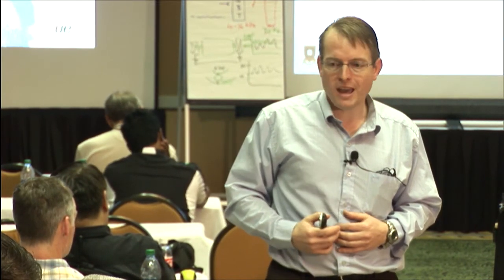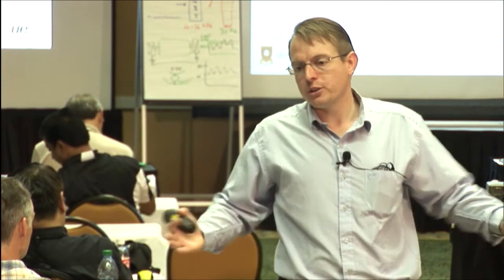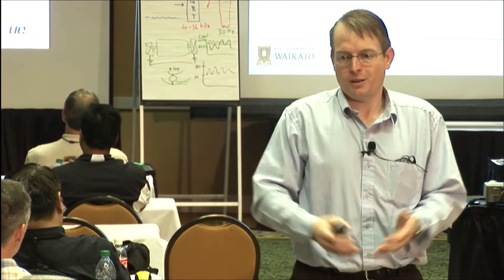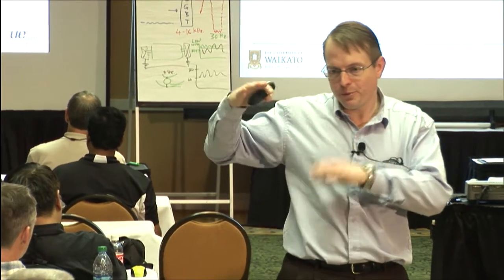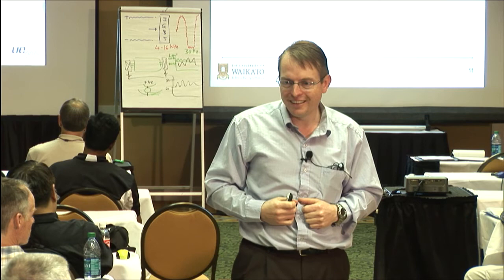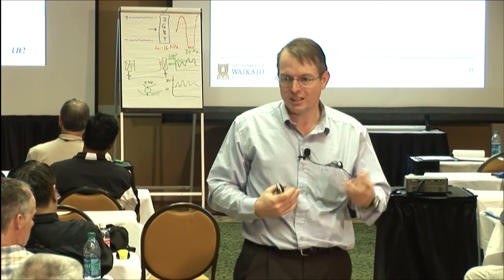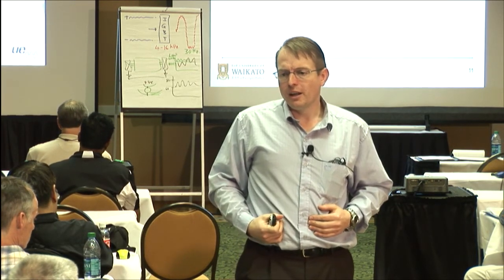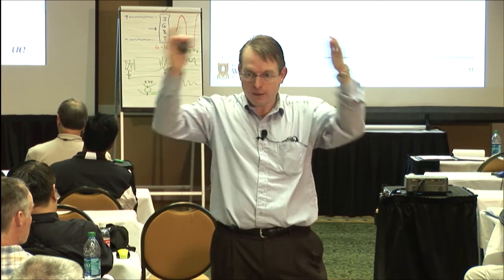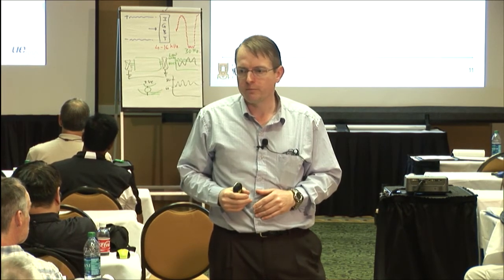I refer to that as the poor man's VSD. To give you a really good example, you could have a 300 kilowatt variable speed air compressor, or you could have 10 30 kilowatt fixed speed compressors, okay? You could set them all up on a pressure cascade control, and you'd have effectively what I would refer to as a poor man's VSD air compressor. But in terms of operation stability and maintenance, you're maintaining one piece of equipment instead of having multiple. So I think even the immediate capital cost might be line ball, but if you take a step further back and look at the big picture in terms of life cycle cost and stability of control, I would go with the variable speed controlled option every time.